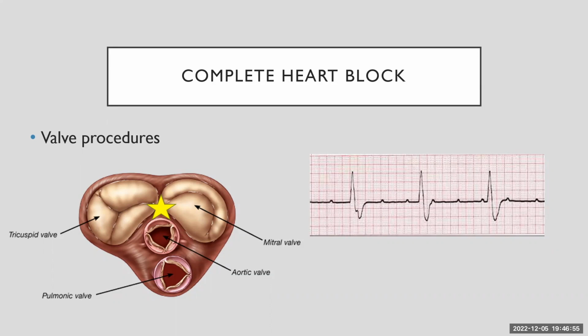Whereas typically the mitral valve ring is a complete circle. What you see for the tricuspid valve is an incomplete circle. And the reason for that is that the space that you see in that is positioned at the point where you would typically find the AV node, because it is very intimately related to the tricuspid valve. And so that is the reason why tricuspid and mitral valve annuloplasty rings look different. And this is to try to minimize the risk of injuring the AV node.